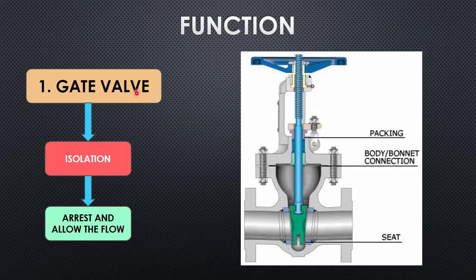Let's start with the first valve — the gate valve. The purpose of the gate valve is isolation: it is used to arrest and allow the flow. Looking at the cross-section schematic, you can see the wedge inside. When the handle is rotated clockwise, the wedge comes down to arrest the flow; when rotated anticlockwise, the wedge goes up to allow the flow.